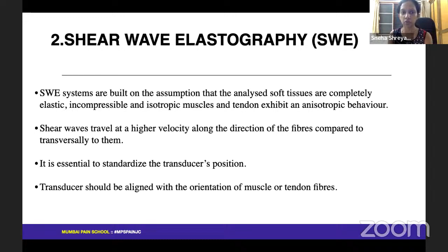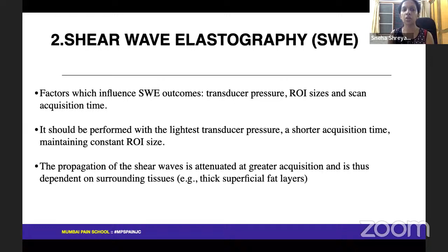The factors which influence the outcome are transducer pressure, region of interest size, and the scan acquisition time. This should be performed by using lightest transducer pressure, shortest acquisition time, and maintaining a constant ROI size. The propagation of shear waves is attenuated at greater acquisition depth, so this is dependent on the surrounding tissues.